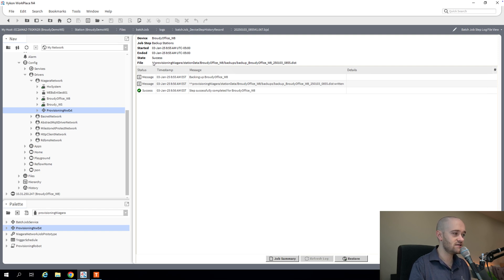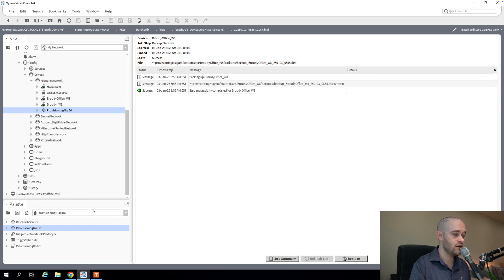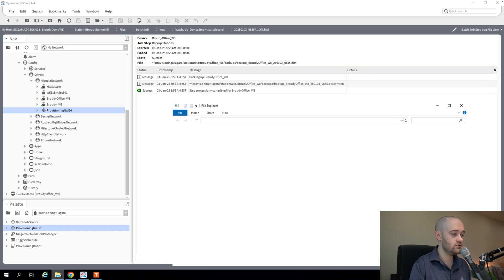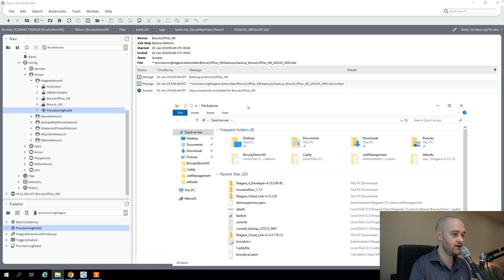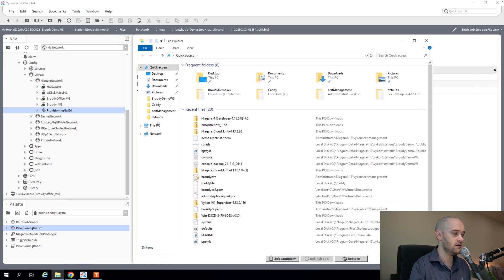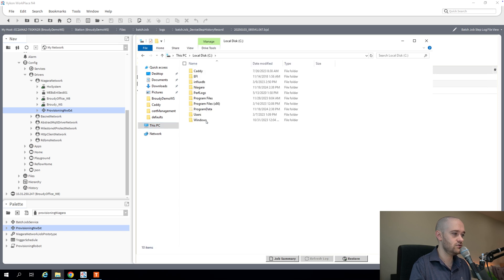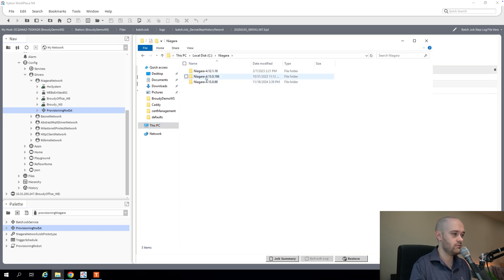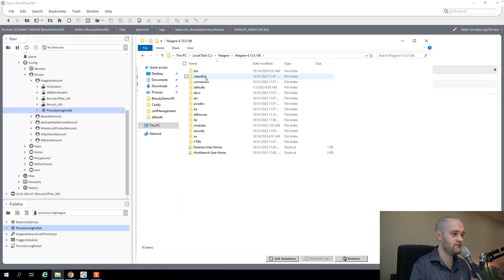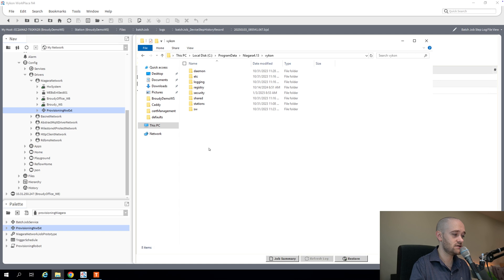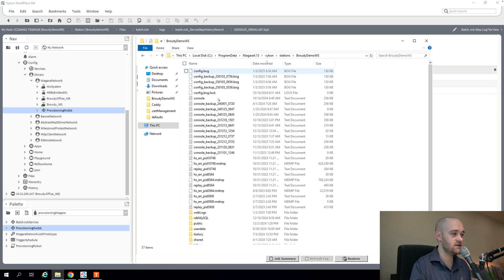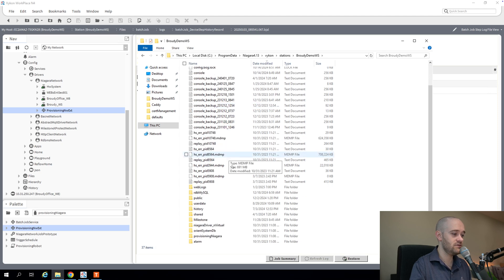If you're familiar with modifying your login pages for Niagara, you know these double arrows indicate protected user home, which is the directory above the station that we're typically used to seeing from within Niagara. So if I go into my Windows File Explorer now and we navigate to our particular install of Niagara, we're going to the daemon user home because we want the station that's actually running. And we go into our stations and then the station itself.